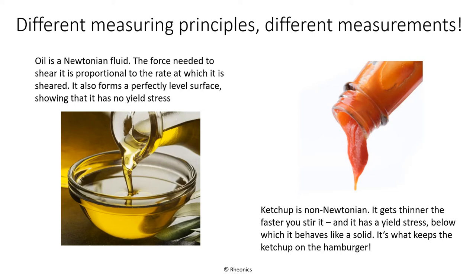Viscosity is a somewhat misleading term, because it suggests that it is a fixed property of a fluid. But only a small minority of fluids have a fixed value of viscosity — these are called Newtonian fluids. The viscosity of a Newtonian fluid is independent of the rate at which it is sheared; therefore, almost all viscometers will measure the same viscosity regardless of the measurement principle. Typical Newtonian fluids include water, pure vegetable and mineral oils with no additives, and sugar syrups. The vast majority of fluids are non-Newtonian. The reading of a viscometer in a non-Newtonian fluid depends on the shear rate with which it is measured. Ketchup is a strongly non-Newtonian fluid — the reading it gives with a viscometer depends on its measuring principle as well as the shear rate that it produces.